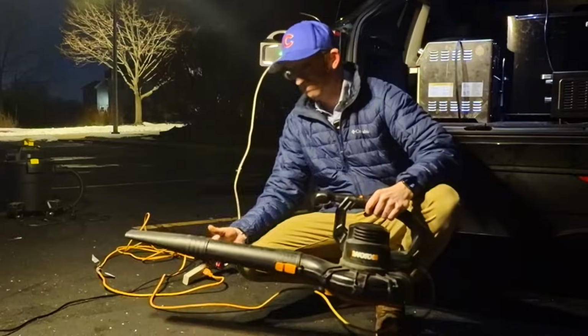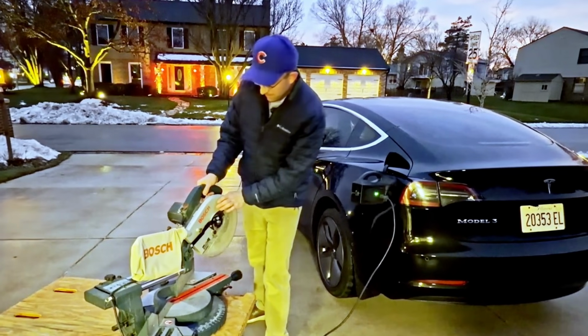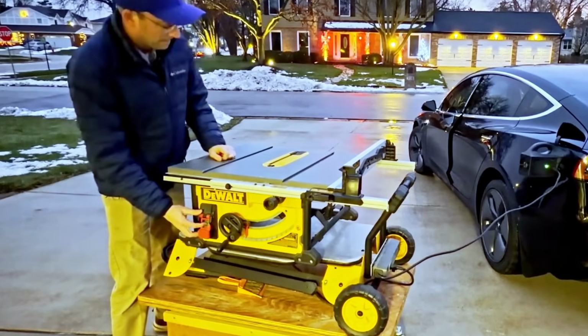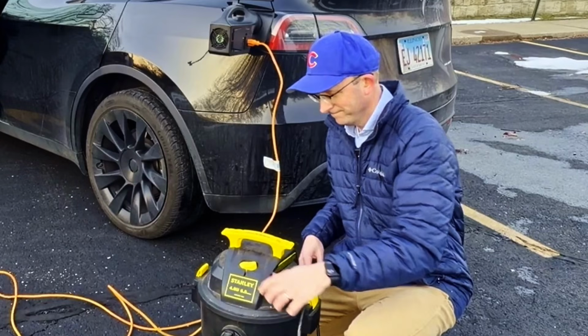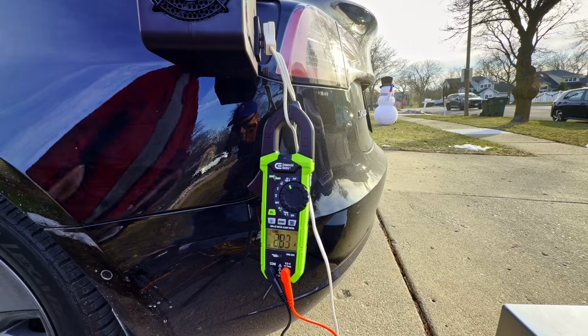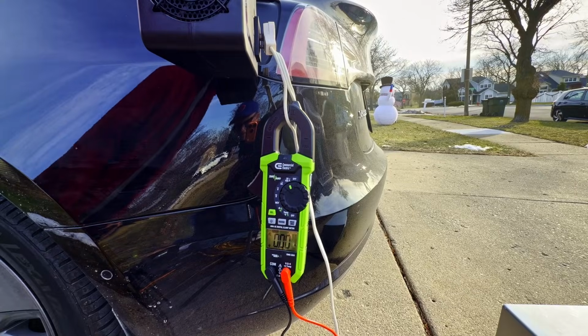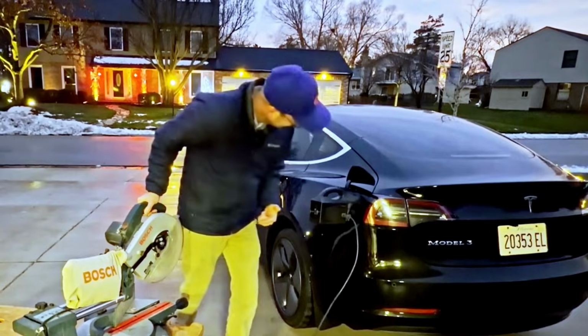I've tested a leaf blower, two different power saws, and also a shop vac. In all of those cases, the device shut itself off the minute the current peaked. That indicates the inrush is hitting the breaker's fast trip threshold, not the continuous one. I was curious what level that current was peaking at.